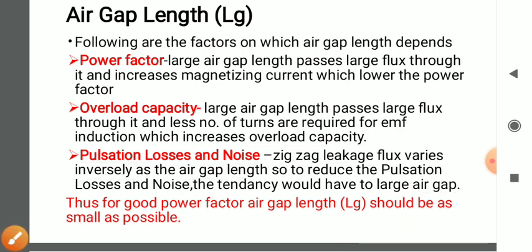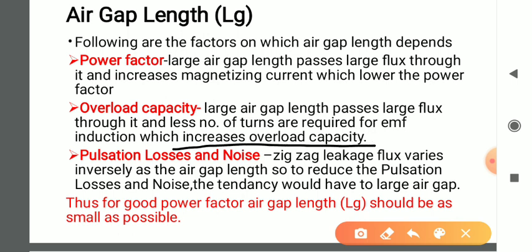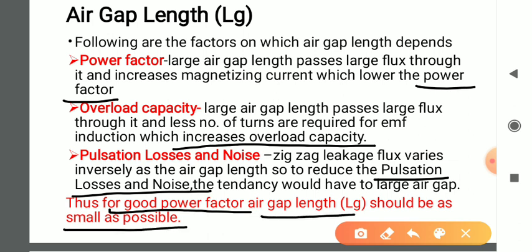If we maintain a large air gap, we get increased overload capacity and the pulsation losses and noise become reduced, but we need to compromise with the power factor. Therefore, the power factor is a very important factor which directly affects the performance of the machine. Whenever we need to design a good power factor machine, we have to go for the minimum possible length of air gap. With minimum possible air gap length we get a design of good power factor, and in other words, good efficiency.